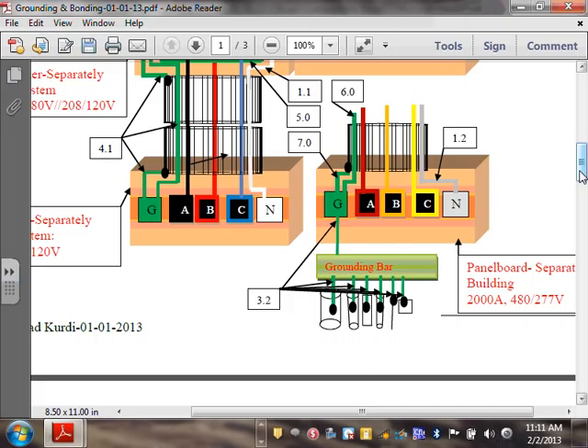The code says on the load side of the service disconnect means you cannot bond at all, with the exception of a separately derived system. We'll talk about that one in a second. No bonding. Any comments, guys? Any questions about this? So that's how you bond and ground a separate building. Does that make sense? Is it too simple? Am I just wasting your time, guys, or no?